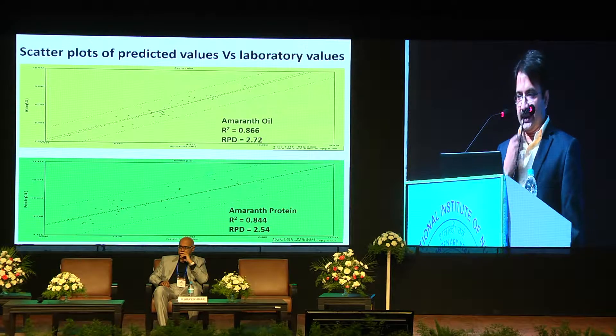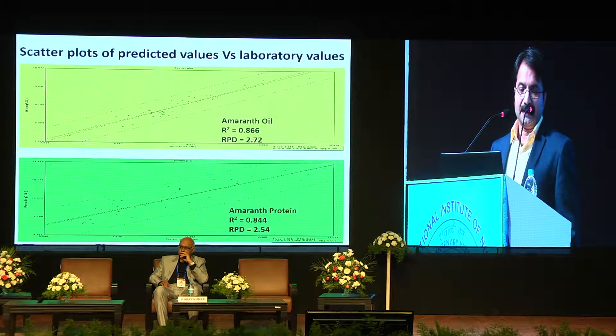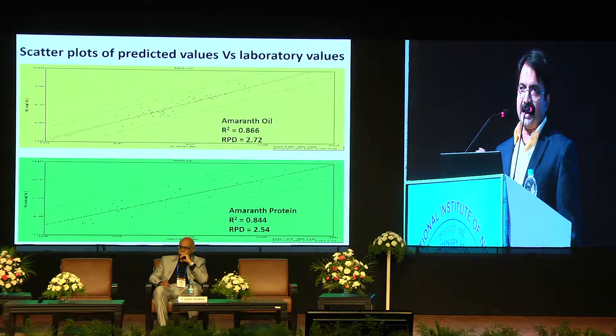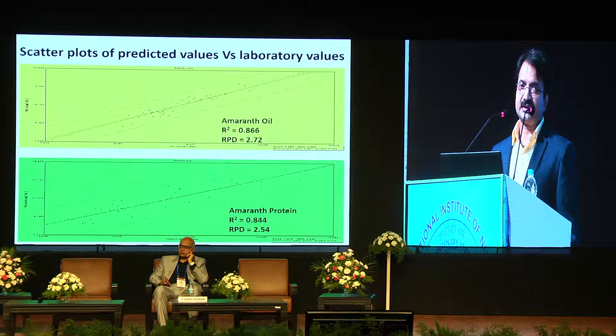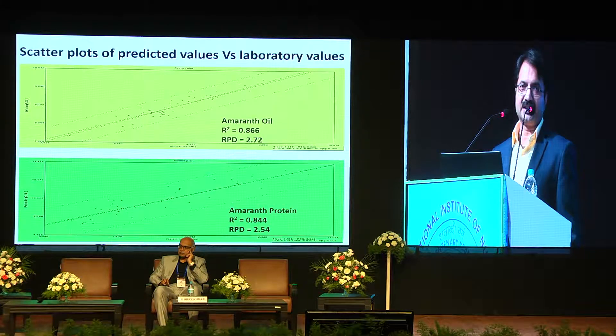In the results, the scatter plot for amaranth oil shows the NIR predicted value on the x-axis and the actual laboratory value on the y-axis. There is good agreement between the lab value and the predicted value for both oil and protein.